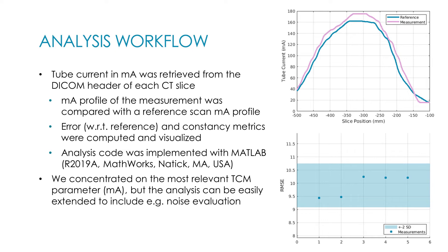Our code was implemented in MATLAB and it simply extracts the tube current from the DICOM header of each CT slice. The mA profile of the scan can then be compared with a reference scan and different error and consistency metrics can be computed and visualized over time.